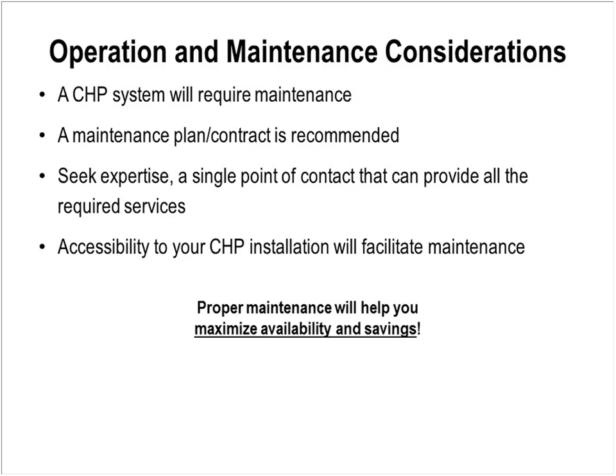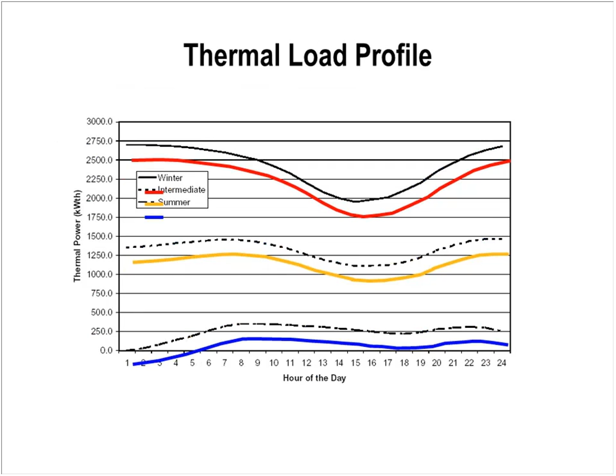The red line down below is the heat, or winter use, of that load profile. If it's not coincidental with the thermal load—which in this case is the hot water being highest in the winter when the electric load was lowest—you'll have challenges with it. So you need to make sure that heat recovery is on a coincidental basis.